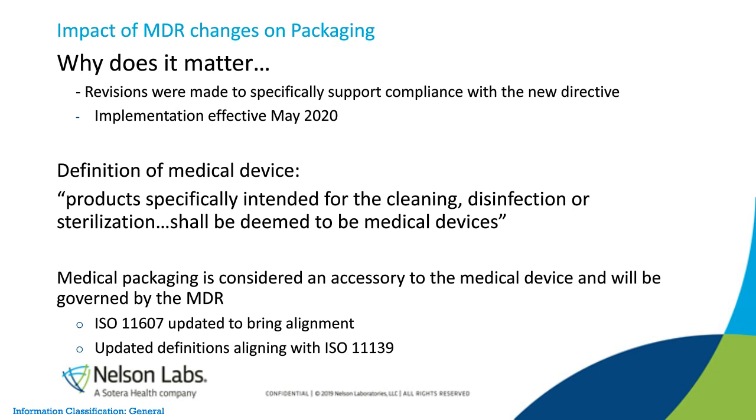For example, the definition of a medical device has been updated so that products specifically intended for cleaning, disinfection, or sterilization shall be deemed to be considered a medical device. This includes accessories such as packaging materials. Medical device packaging is the accessory and therefore is governed by the MDRs. That's why the 11607 was updated and brings it into alignment, and these definitions are now concurrent with ISO 11139.